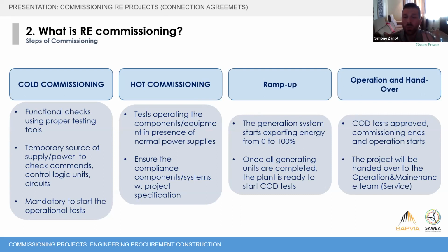In hot commissioning is when the blades of the turbine spin for the first time and generate electricity for the first time - first generation, first synchronization. But the plant doesn't go from 0% to 100% of generation. There is an interim part called ramp up, where portions of the plant are commissioned step by step, and checks are carried out to make sure the performances are always met.